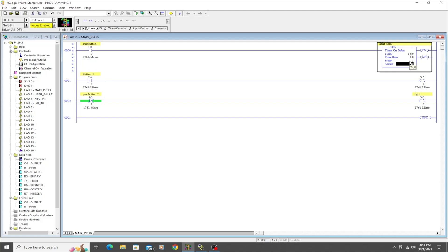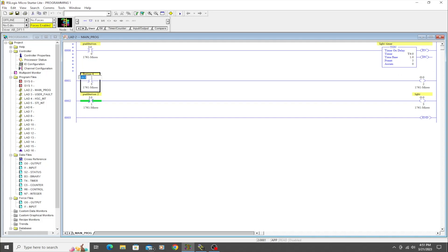Now at this point, if we were to download this program and hit this button, so this goes green and starts passing the logic over, it's going to start timing this timer. When it hits five seconds, this timer is going to quit timing, but then nothing else is going to happen because we haven't used any part of this timer anywhere else in the program for it to actually do something.